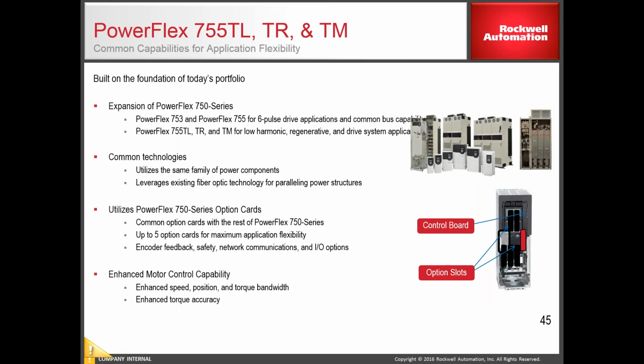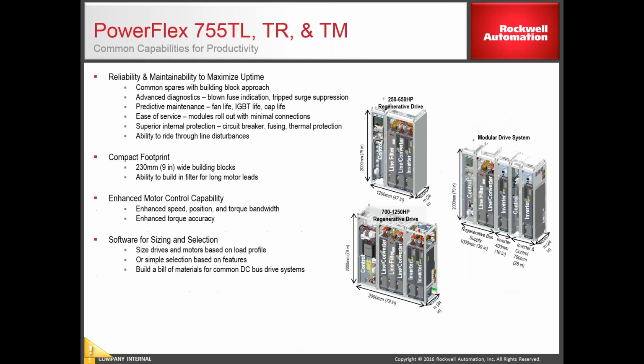So again, it's an expansion of the 750 product, okay? Common technologies. It's going to use a lot of the same components, the I/O modules. All those modules are going to be the same. The option cards. And in terms of premier integration, if you run a ControlLogix system, there's a lot of features and benefits that you get from the whole premier integration story. I mean, there's automatic device configuration. This is where if you have a drive that fails and you have to change it out, if it's tied to a ControlLogix, the configuration for the drive is stored in the ControlLogix, so you can have ControlLogix automatically reconfigure that drive once you bring it online. So all those features and functions apply to this new 755T product.